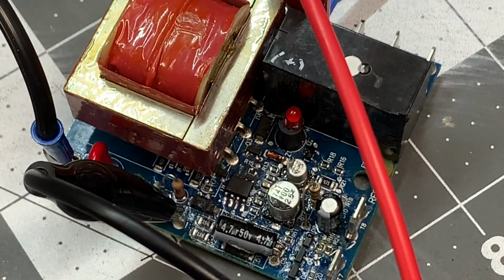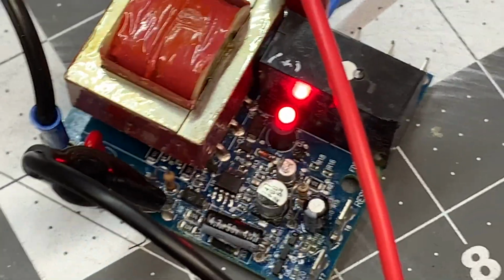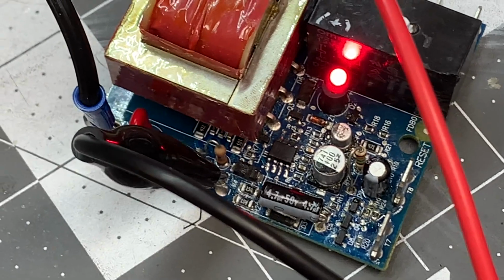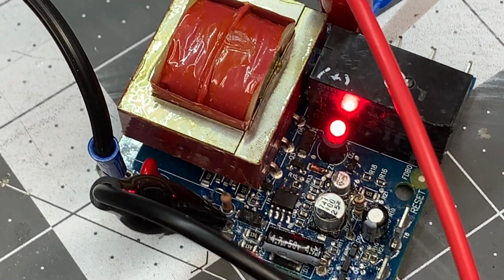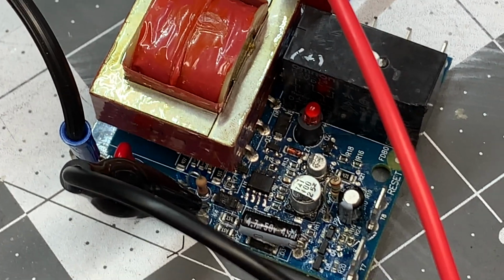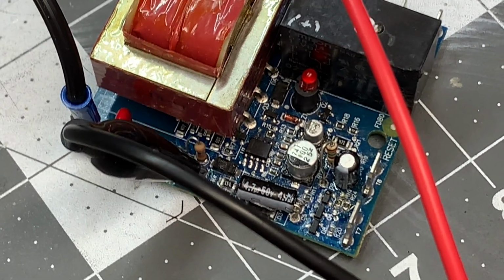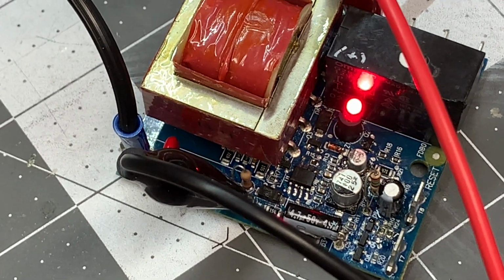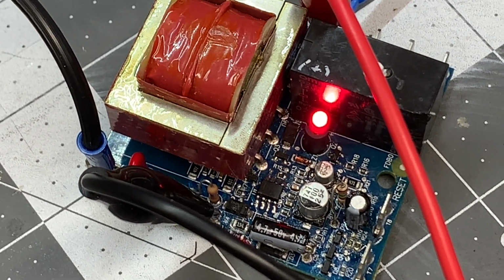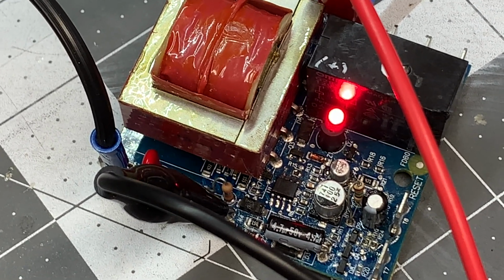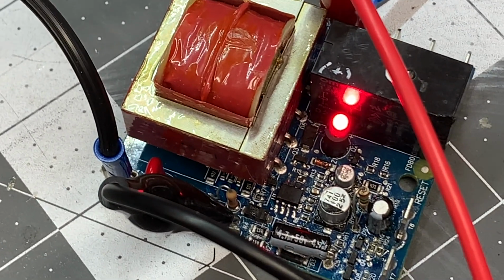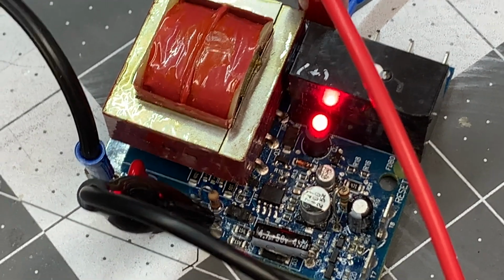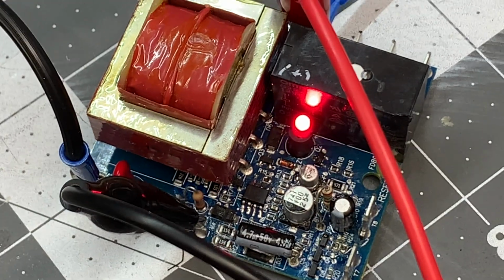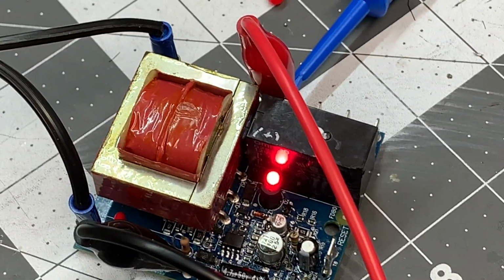Let's simulate that. We're going to turn the power on right now, and we've got power and the relay clicked. If I disconnect, or simulate a low water condition, after about 5 seconds it's disconnected, the low water cutoff. If I reconnect or refill the water, the LED comes back on and re-engages the circuit. So I'm going to disconnect again: 1, 2, 3, 4, 5, and it goes out. So there we have it.